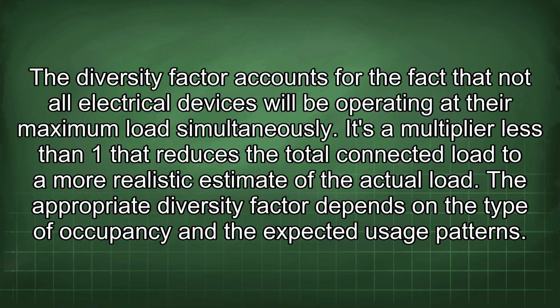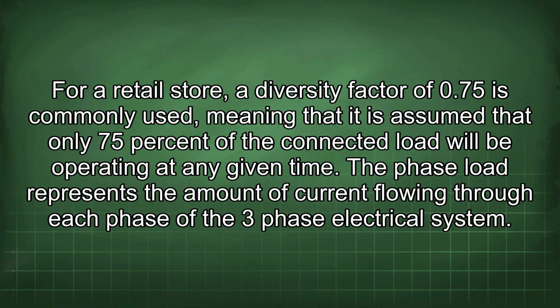The diversity factor accounts for the fact that not all electrical devices will be operating at their maximum load simultaneously. It's a multiplier less than 1 that reduces the total connected load to a more realistic estimate of the actual load. The appropriate diversity factor depends on the type of occupancy and the expected usage patterns. For a retail store, a diversity factor of 0.75 is commonly used, meaning that it is assumed that only 75% of the connected load will be operating at any given time.